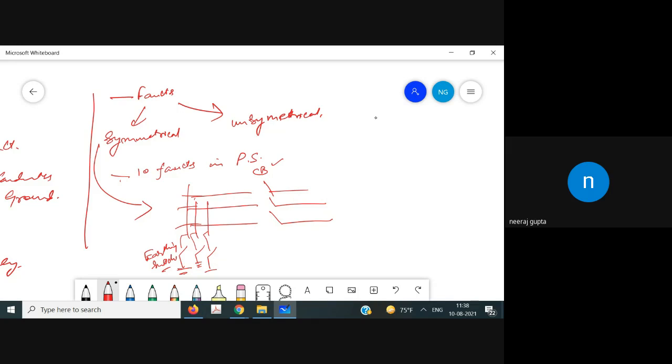Let us suppose that we have de-energized the line, and we want to energize it. For energizing the line, the earthing switch should not be connected. If it is connected, in that case there is a triple line fault. This switch should be off. If not, then the triple line fault occurs. This is one example, due to the wrong coordination between the circuit breaker and the earthing switch.